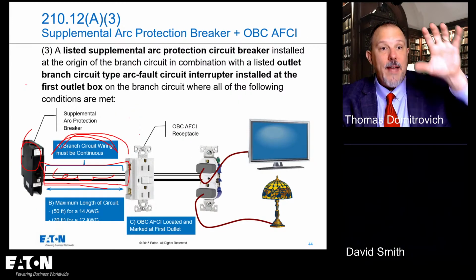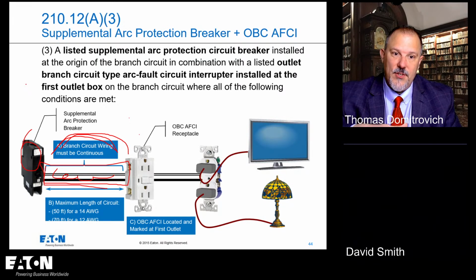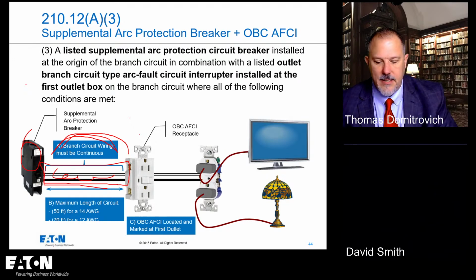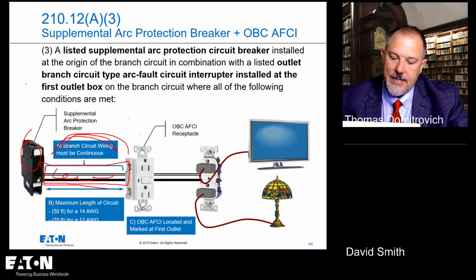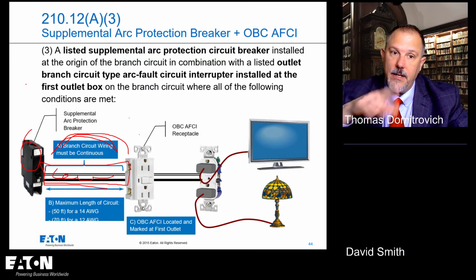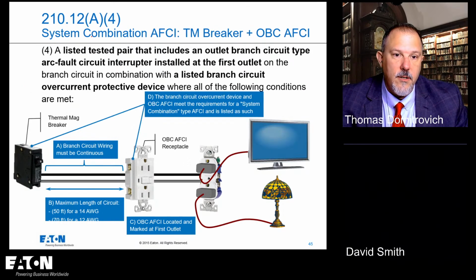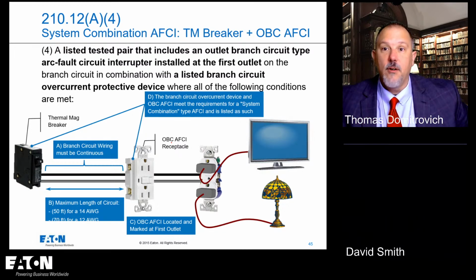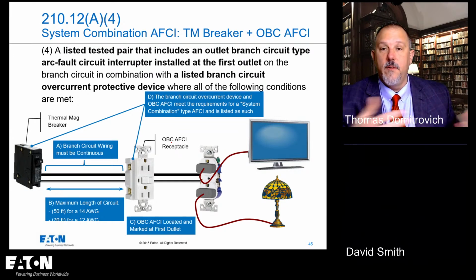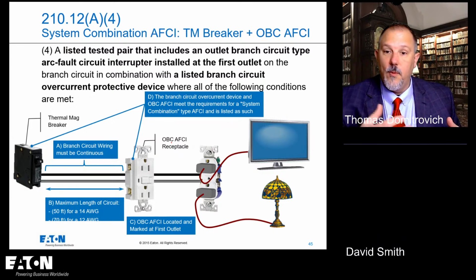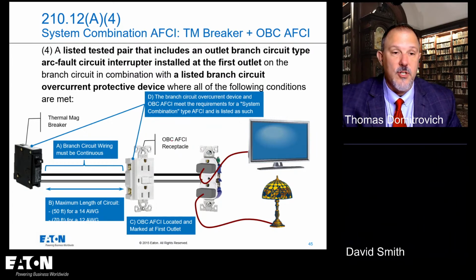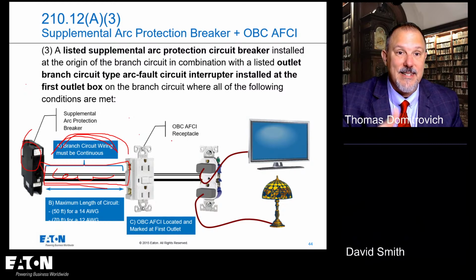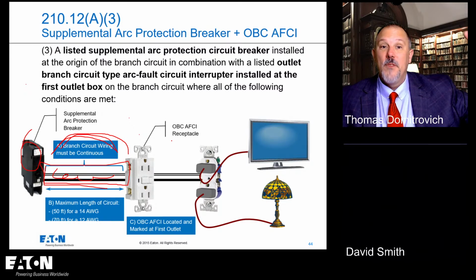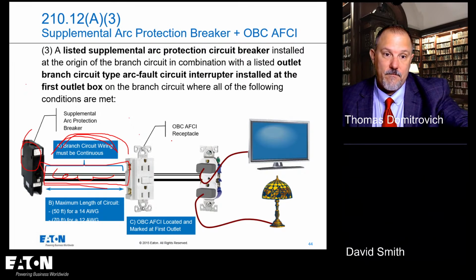Okay, so what happened was we had all of this research, all of these research papers, all of this data. Code Panel 2, Task Group 2 sat down, and you've got a lot of people arguing about providing options. And so we started with this one, saying, okay, we bring a pair of devices together. The breaker guys said, we don't want to reduce protection. We want to provide the equivalent protection. So we want to list these things together. And the receptacle people said, we don't want them to govern the decision on whether or not something can be brought to the table. So we ended up with a 3, which was a listed supplemental arc protection circuit breaker, because the circuit breaker guys said, look, we can list a breaker that will provide that protection of the home run circuit.